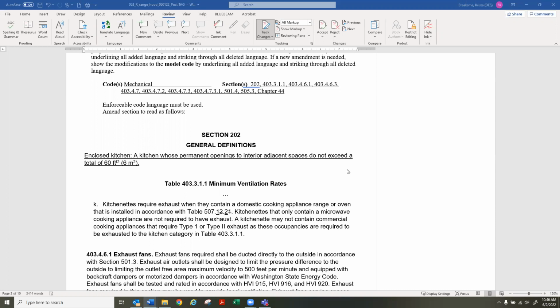Eric? Yeah, what we typically see, we've done a lot of multifamily housing, everything from low income to high-end apartments. I would say 95% of them are using ducted range hoods right now. We've done one project, which is a low-income housing project in Seattle that went passive house that used recirculating range hoods. Again, you're still required to have a recirculating range hood above the appliance, or a recirculating microwave above the range, so all you're saving is a little bit of ductwork and a wall penetration. So it's pretty minimal cost, because you already have to have the hood. And most of the hoods are convertible from being recirculated to ducted already.